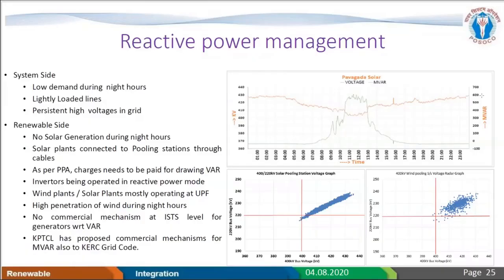Earlier, the southern region was by default a low voltage scenario. Maybe some PPAs were made that way, and that became a standard and continued. Now, what does that mean? That means the generator is not going to absorb anything. Either he will inject or he is going to operate close to UPF. That means he is going to add a problem to us. And another aspect is there is no commercial disincentive for MVAR absorption or injection, even at ISTS level.